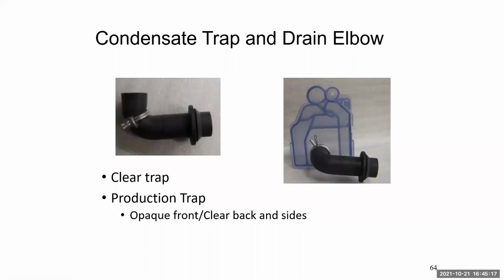Condensate traps and drain elbows. If you take a furnace out that's still got a good drain elbow on it, put it in your truck. Save it for later. You will use it. Those things dry rot, they crack, and that will be a 2 o'clock in the morning call for you that somebody woke up and they got a puddle of water on their floor. Save those elbows off of other furnaces if they're in good shape.